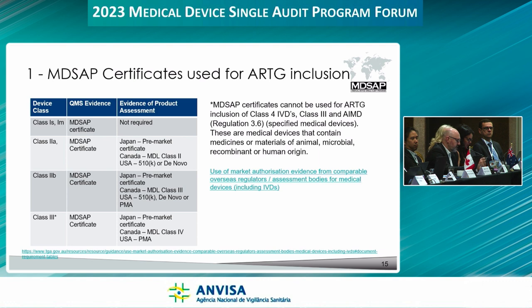And as we increase the classification of device, there's additional product assessment evidence required. So the table there shows for the lower risk devices, for example, a US 510K can be used. And for the higher risk ones, a pre-market approval would be required from the FDA.